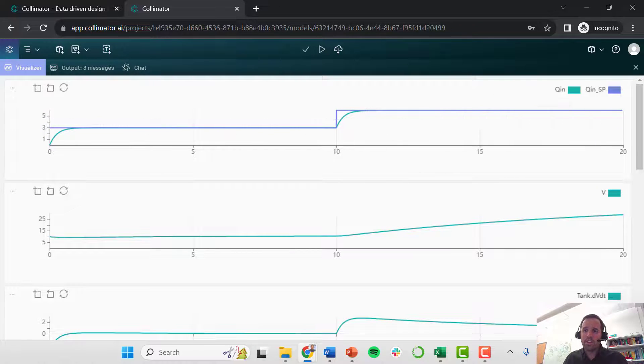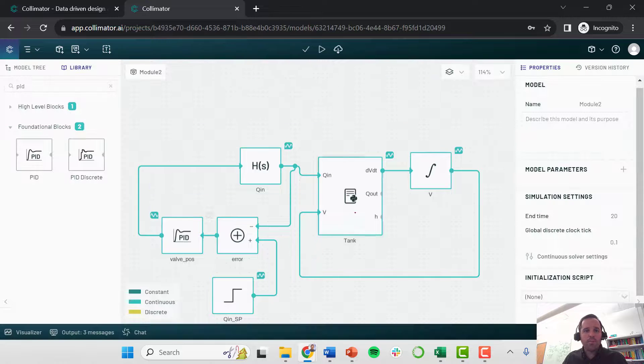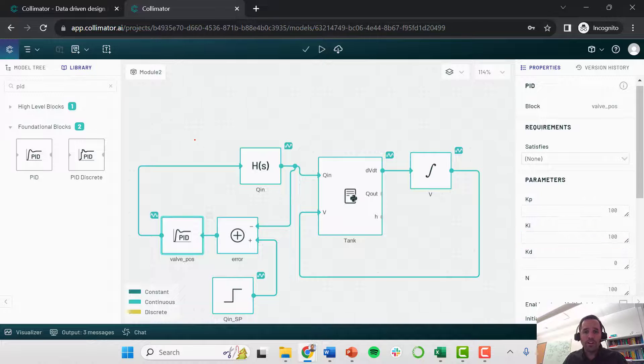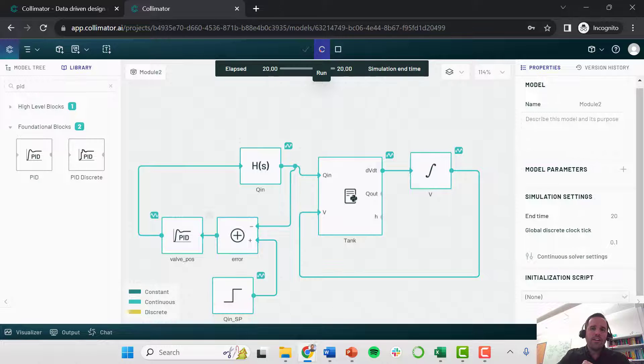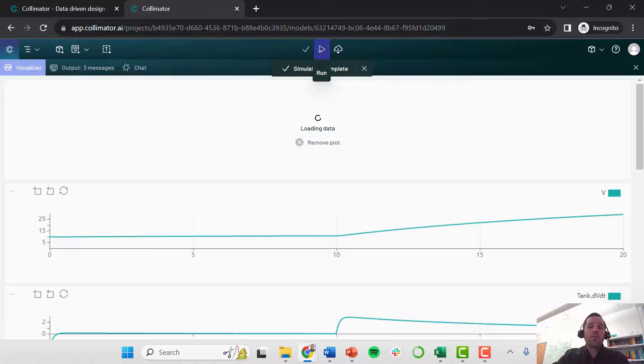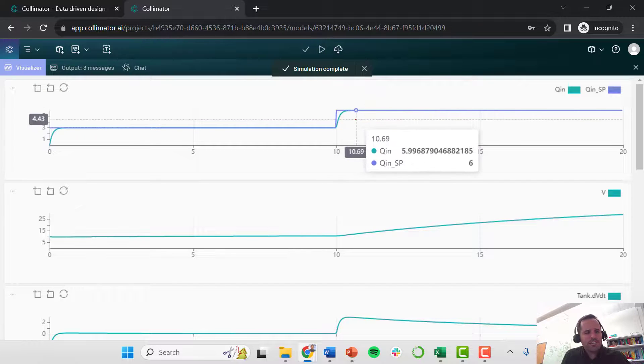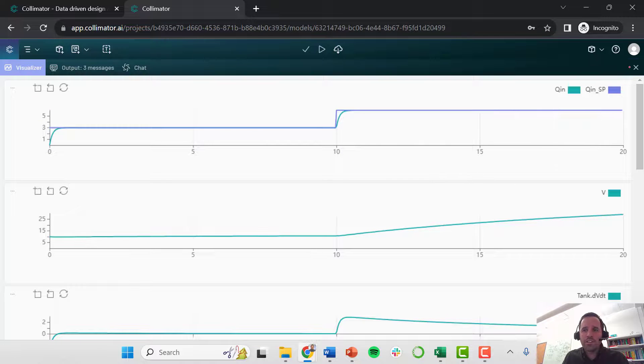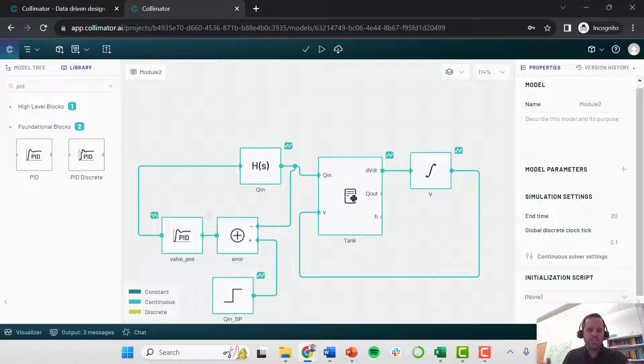Let's see what happens if we make our controller more aggressive. I'll go into the controller and change the gains to 100, which corresponds to a controller time constant of 0.1 minutes. The flow rate now reaches the set point a little faster. You don't want your controller to be overly responsive though — in some cases you can have overshoot, and you also don't want it to be too responsive to noise or to push beyond the physical limitations of your system.